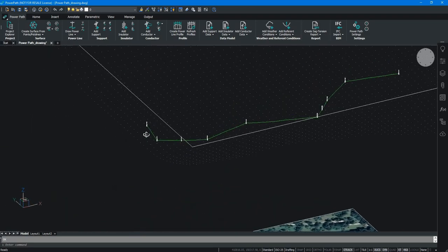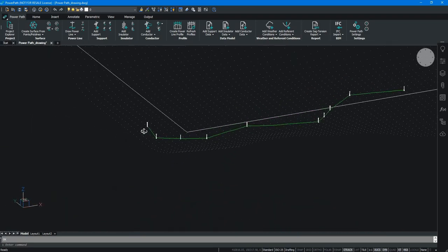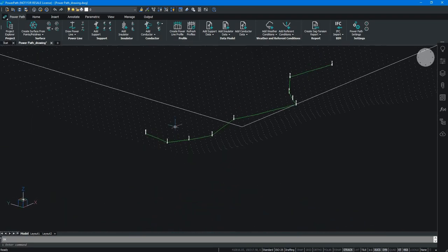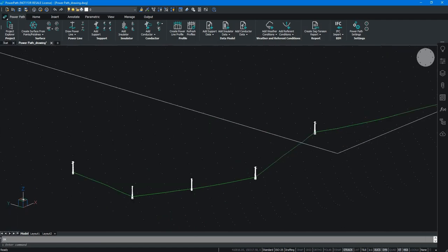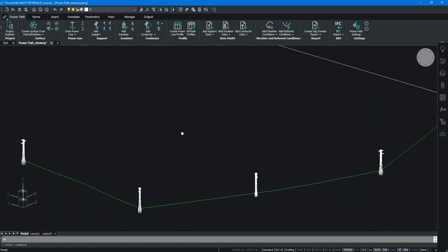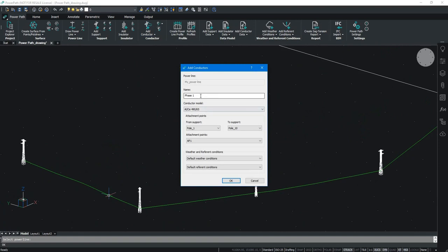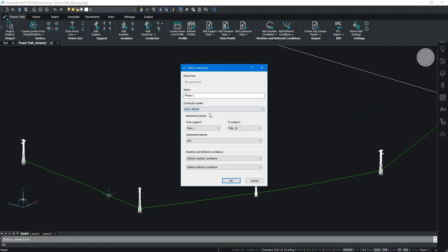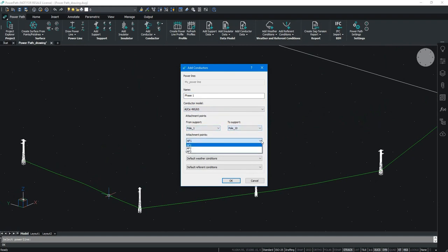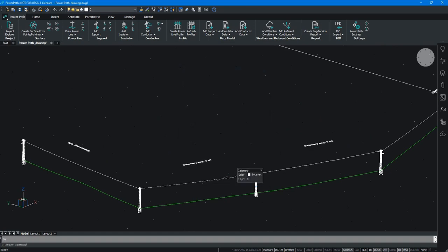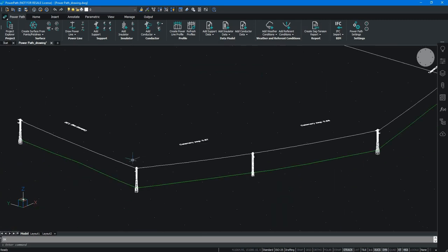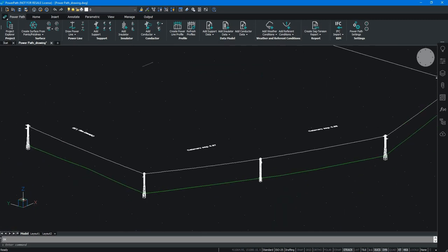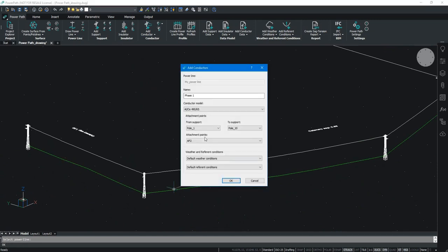After we have defined power line, we have added new supports and insulators and now the next step is to add conductors and ground wire. This is quite simple. We can define the name of the conductor, the model and from which to which support we want to add our conductor. We can also choose for which attachment point we want to add. This means that phase 1 is connected to attachment point 1 and as you can see the conductors are connected to the insulators. Procedure is the same for other phases.